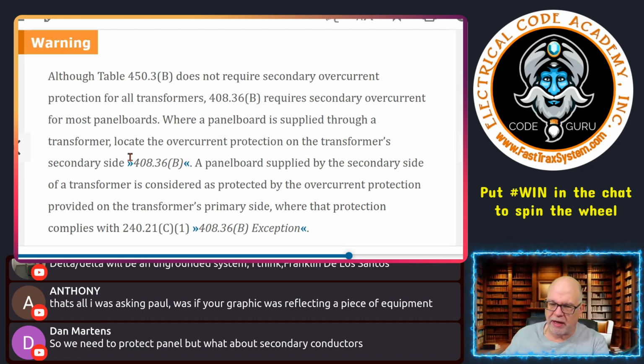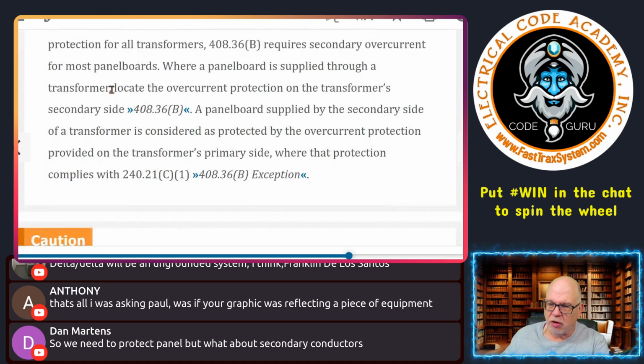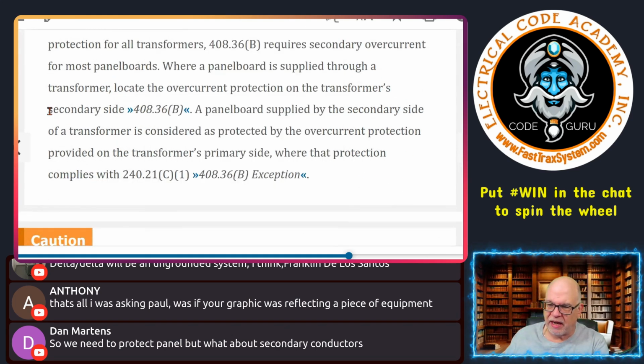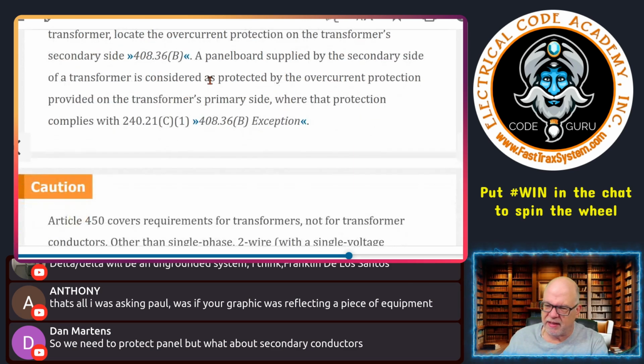It says where the panelboard is supplied through a transformer, locate the overcurrent protection on the transformer's secondary side. It's 408.36(B), and that will be in the panel that it supplies. And it says a panelboard supplied by the secondary side of a transformer is considered protected by the overcurrent protection provided on the transformer's primary side, where that protection complies with 240.21(C)(1).